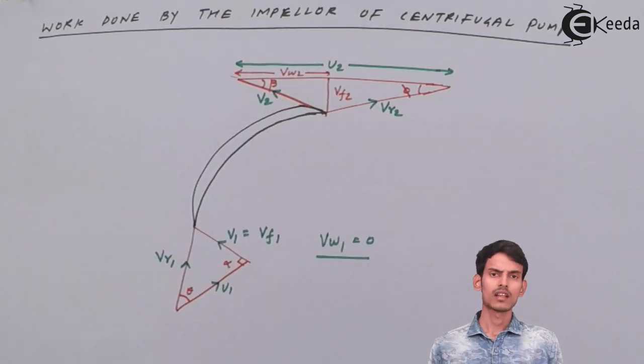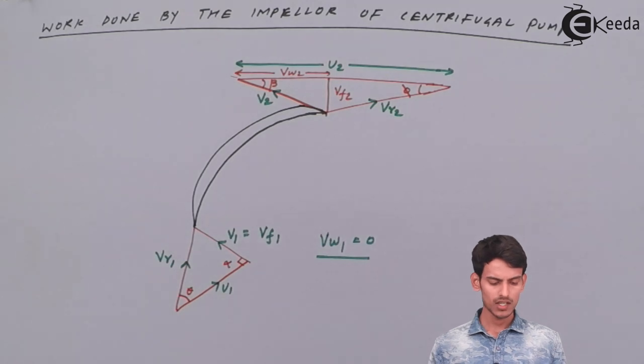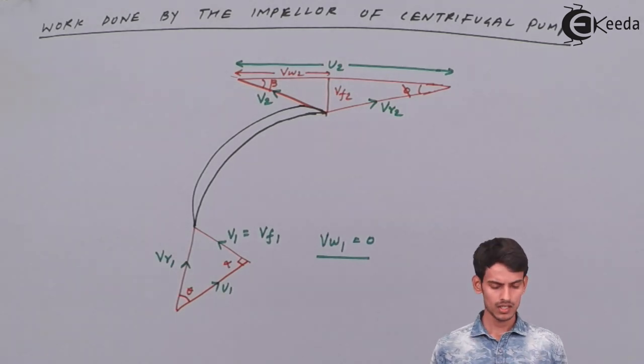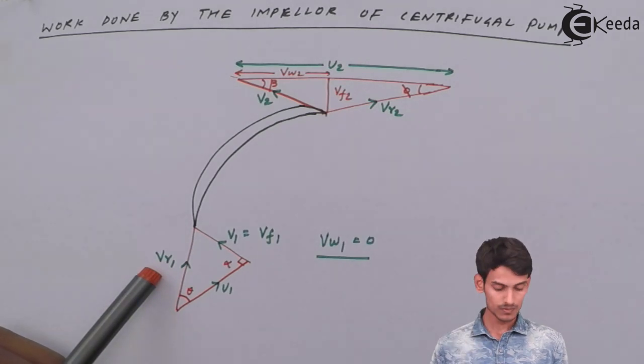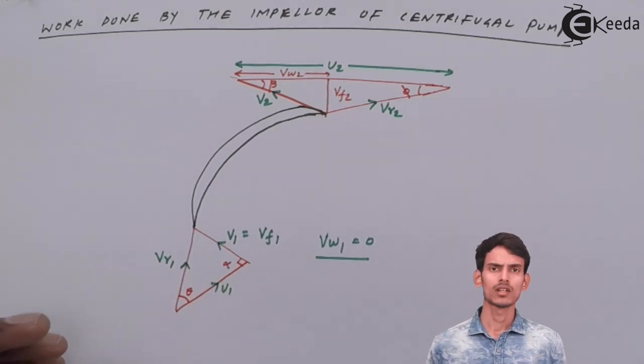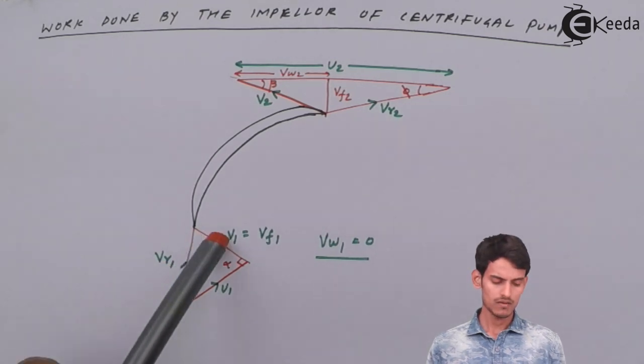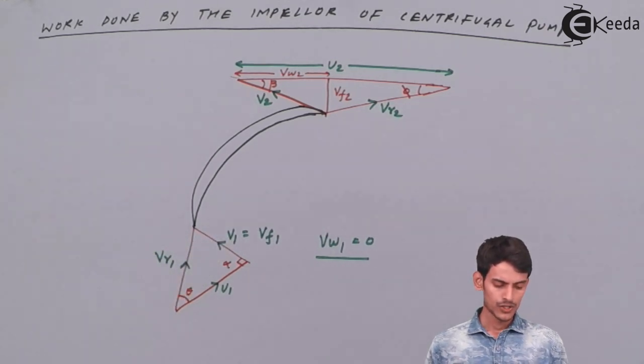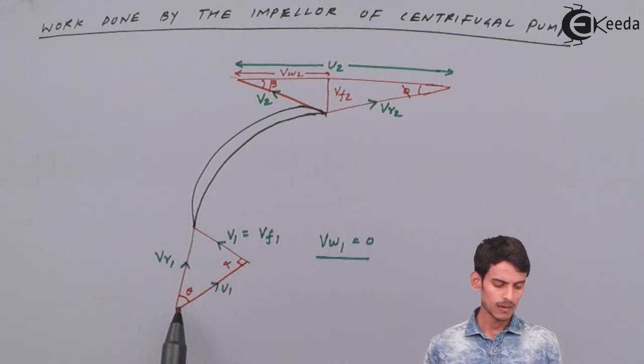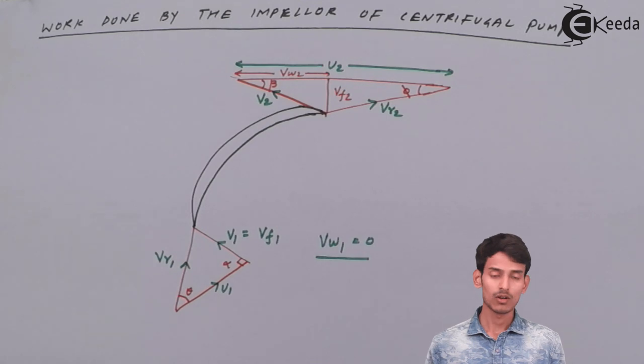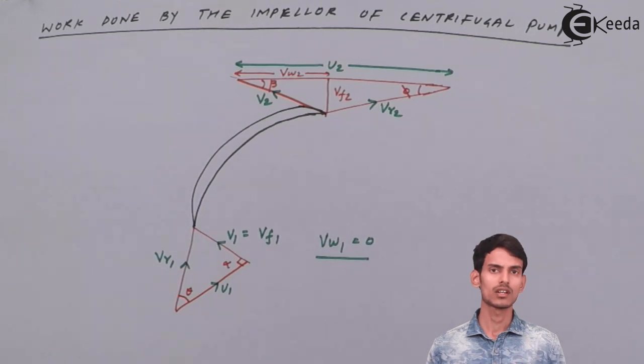The diagram is now complete. We have two velocities at both ends. The absolute velocity is numbered V1, the relative velocity is Vr1, and U1 is the velocity of the impeller at the inlet side. Since the blade is also moving, there comes the relative velocity, and the angles alpha and theta. Alpha is the angle made by the horizontal with the absolute velocity, and theta is the angle made by the horizontal with the relative velocity.